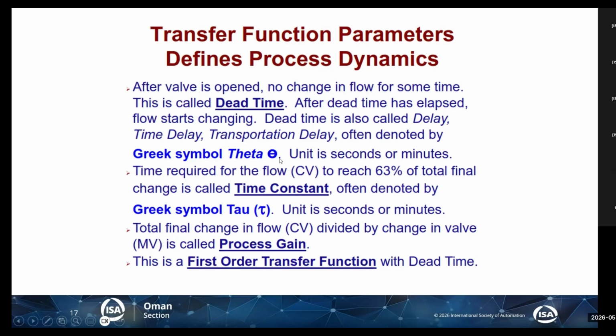We represent that time mathematically as theta, this Greek symbol. The time constant, as I explained, is the time to reach 63% of the desired value when I do the step change. If going from 100 kg to 110 kg is 100%, then 106 is 63%. We represent the time constant mathematically as tau, this symbol. Then we have something called process gain, which is very important. It is the change in flow, the CV, divided by the change in MV, which is normally the valve. And this we call the first order transfer function.